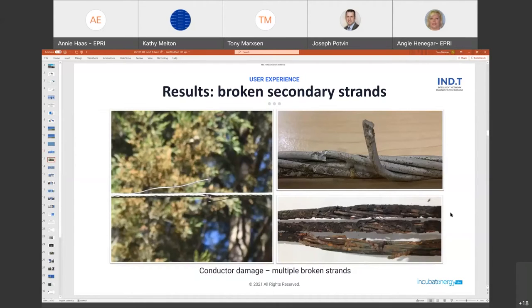We also find them on secondary strands. The thing that we found very early on was that radio frequency signals generated by broken strands actually travel through transformers quite well. So we can locate broken strands on secondary conductors just as well as we can find them on primary conductors. If you look at the photo on the bottom right, that's a local one here.